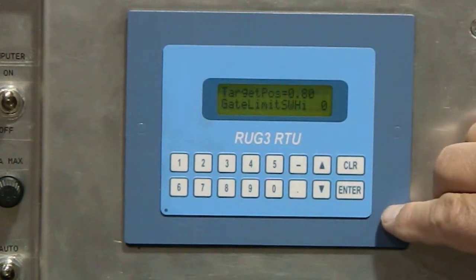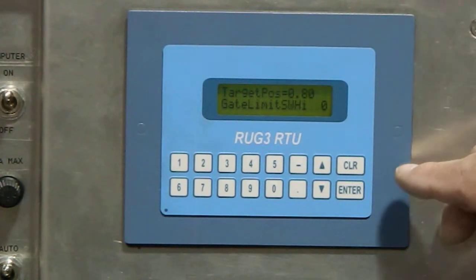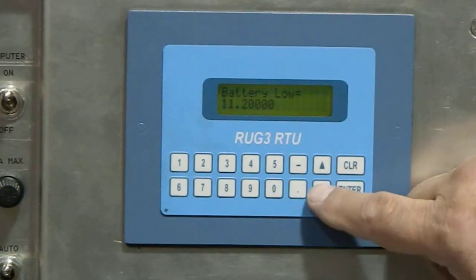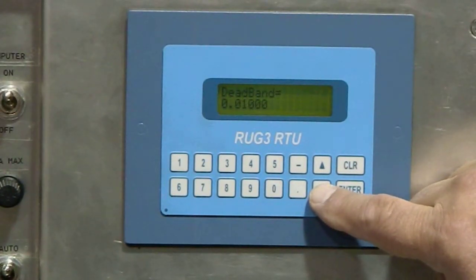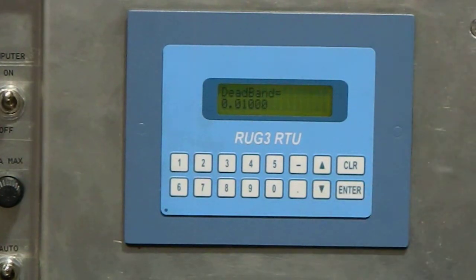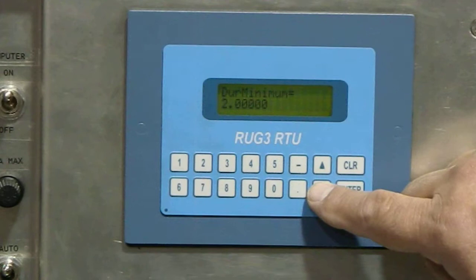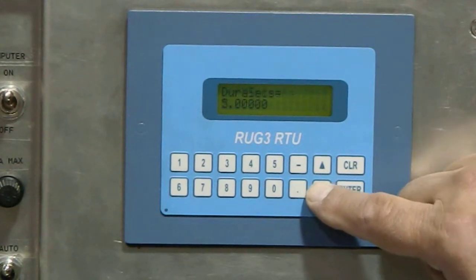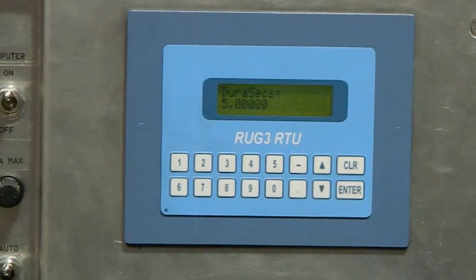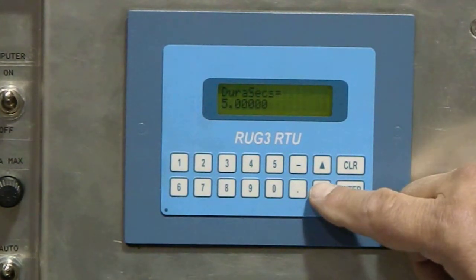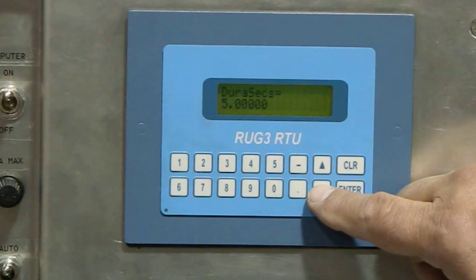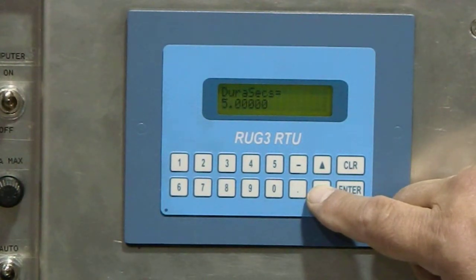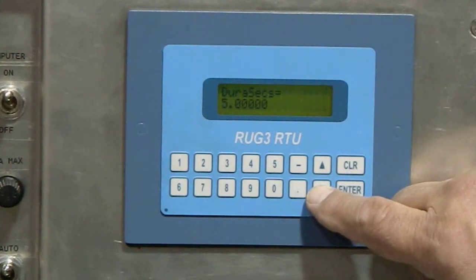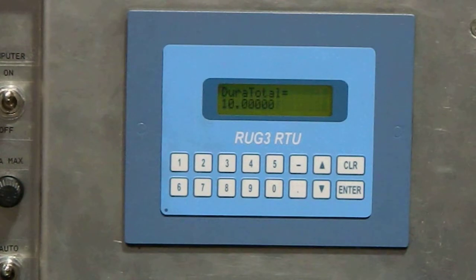We set those in the master RTU, but we can also set them right here by going to set points. This will all be in your manual, and you can deal with targets. Deadband is the plus or minus target that you're willing to accept. The duration is the minimum pulse duration for the motor to move either up or down. In this case, it's 2 seconds. The maximum duration, in this case, the pulse duration is 5 seconds. In other words, if it's a long ways away, it will calculate how far away it is, and it'll say, well, I can actually go to a maximum of a 5-second pulse to try and get there. And the total duration between cycles of taking a look at making an adjustment is 10 seconds.